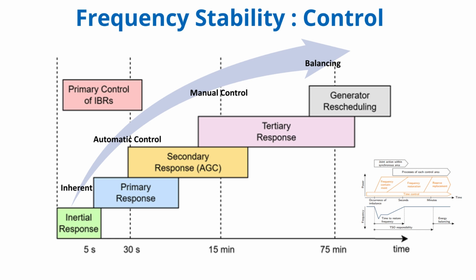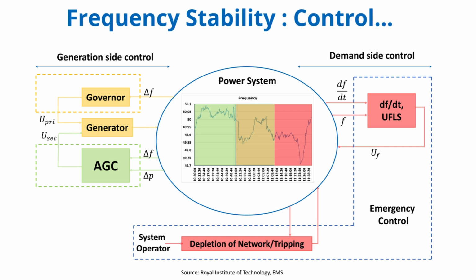The material lists the mechanisms: inherent inertia, automatic controls, governor, AGC, emergency, and manual control. It shows a diagram relating power changes, delta P, to frequency changes, delta F, and the control responses over time, and mentions DFDT. Right, DFDT, rate of change of frequency. That's becoming a bigger concern.